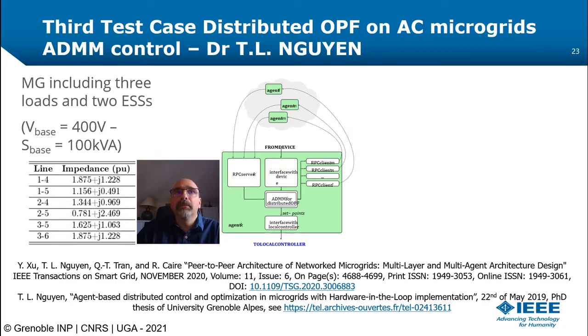Implementation is still the same: the two energy storage units communicate with their neighbors via a client-server RPC interface. Using the values they receive, we run an alternating direction method of multipliers (ADMM) for a fully distributed optimal power flow. Once you get the set point, you give the value to the local controller and move into this control hardware-in-the-loop validation.